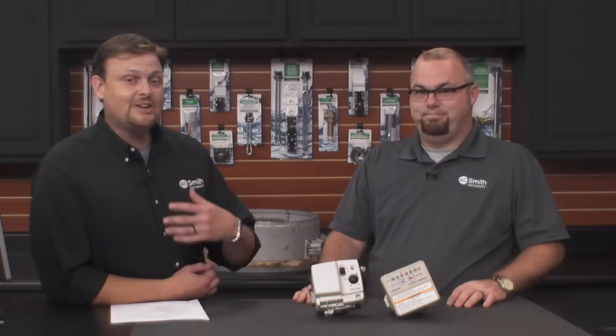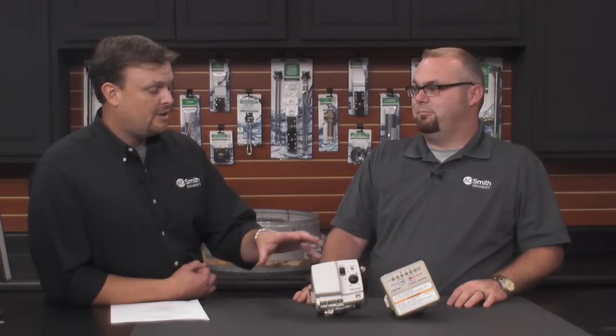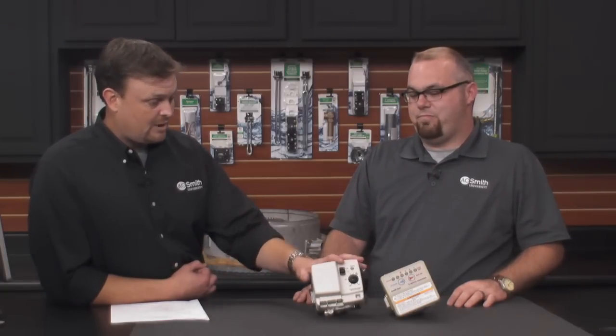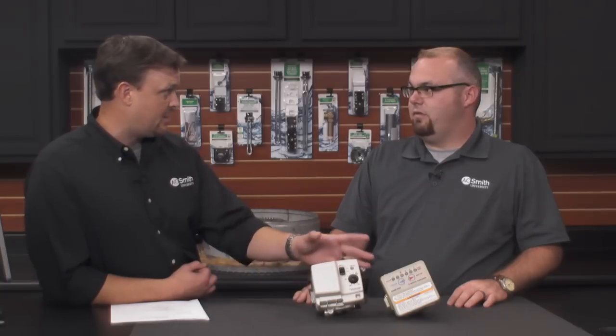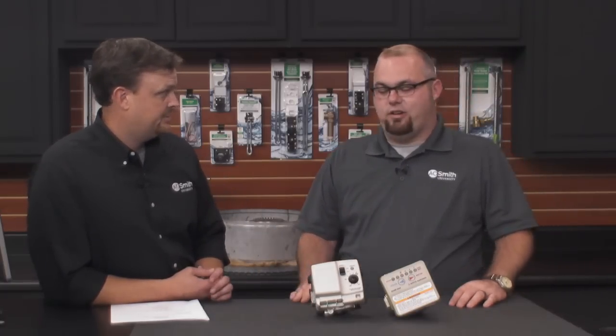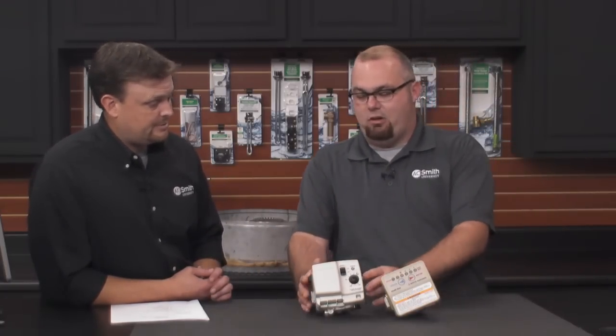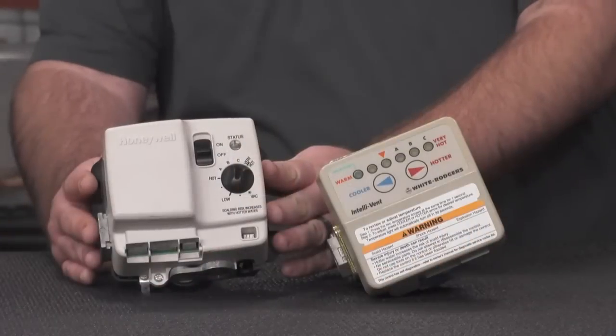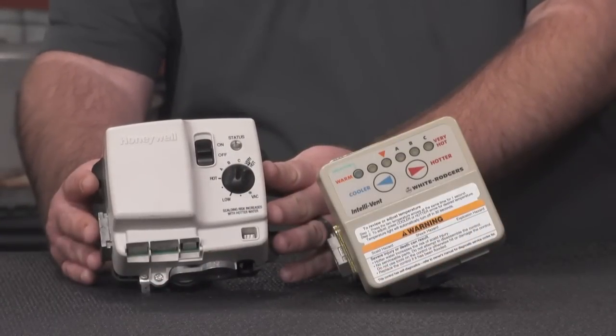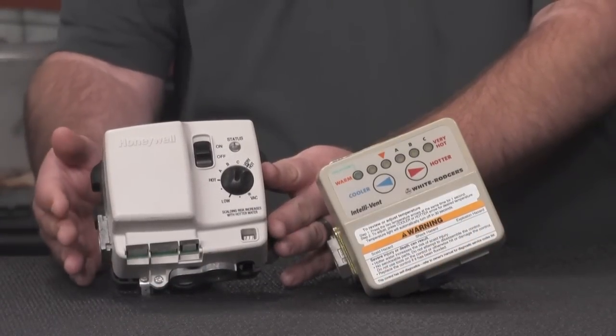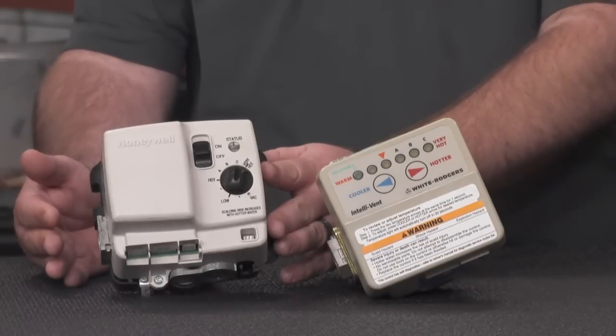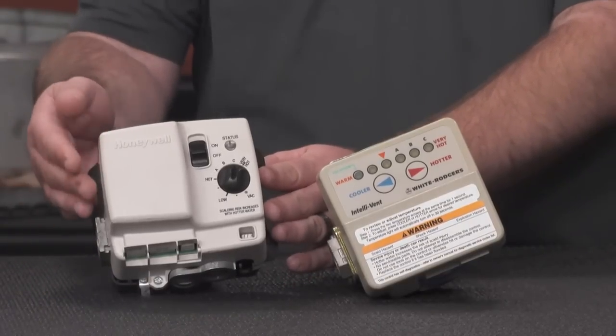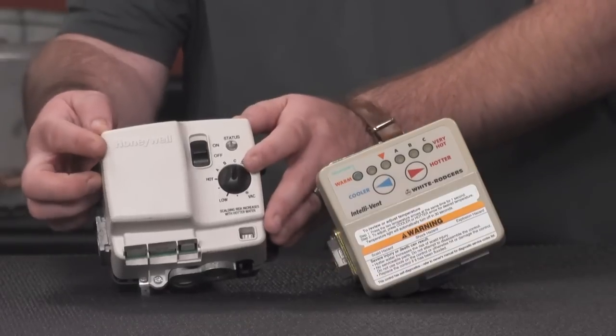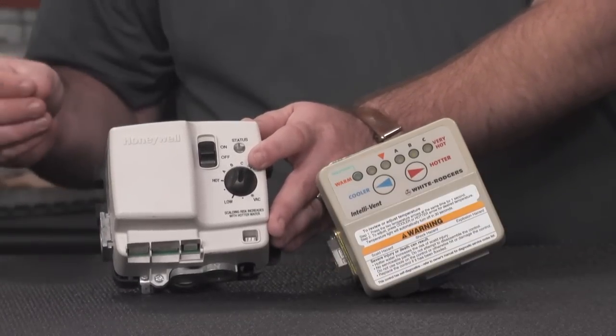All right, so now let's talk a little bit about some of the differences that set this apart from the old. The first thing I want to talk about, because we have it right here on the desk, is the gas valves. They are different. Yeah, the gas valves are different. The new version of the power vent uses the Honeywell control valve, and you can see it definitely looks a lot different. One thing that's different is the way we deliver status codes or error codes. The Honeywell valve has a single LED light that will flash a code at you.